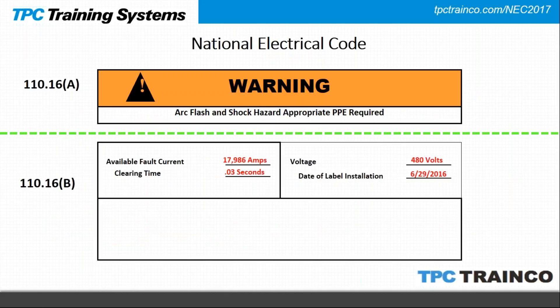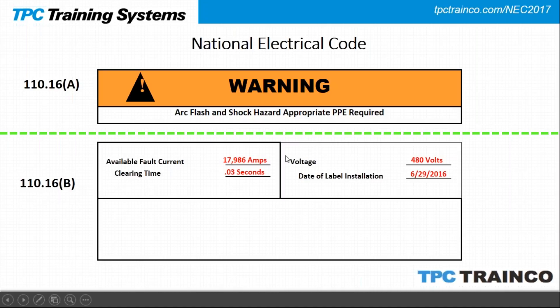An example label shows the difference: the top portion is the generic label we've always had under 110.16 — 'arc flash and shock hazard, appropriate PPE required' — but without specifying what PPE. The bottom portion under new 110.16B now includes the available fault current (requiring knowledge of transformer size, impedance, and voltage), the clearing time from the manufacturer, and the date the label was applied. This information can help initiate an incident energy analysis or select the correct PPE category to protect qualified workers.